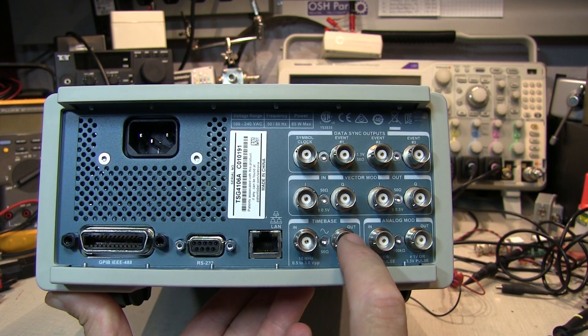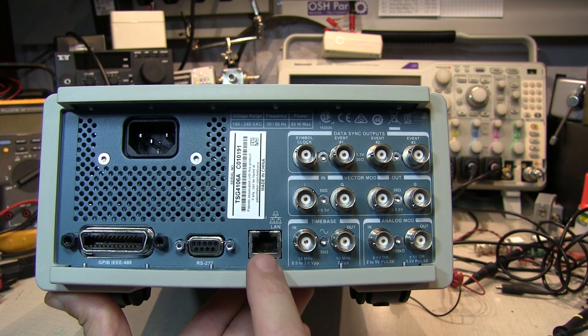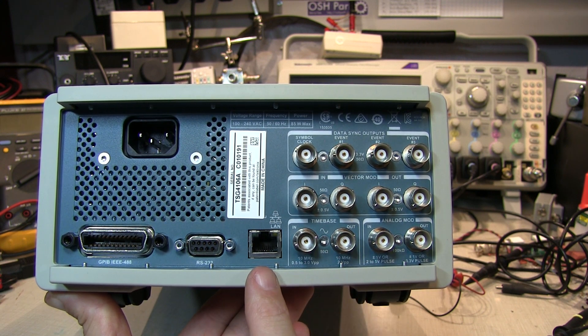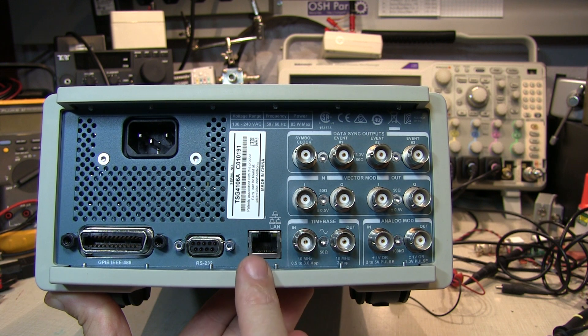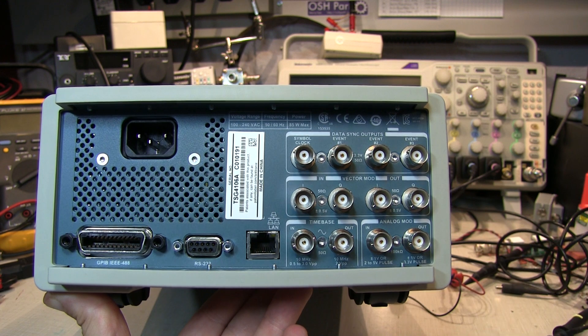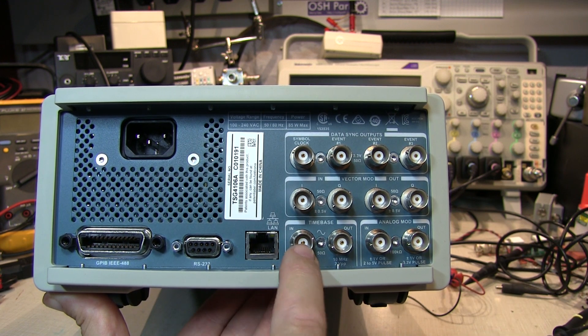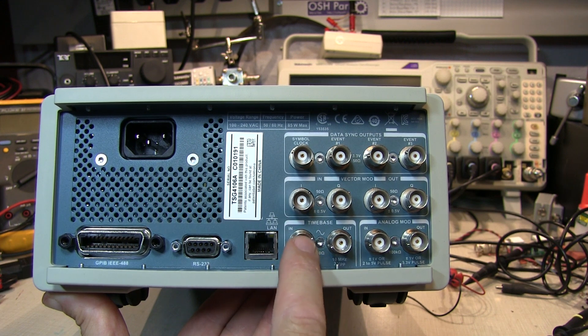There are input and output here for the reference time base. This unit has got an ovenized reference so it's a very stable reference so you most likely use the output here to become the reference for other instruments in the lab. But you do have the ability of tying in an external reference if you've got that in your lab and you want to tie this to that.